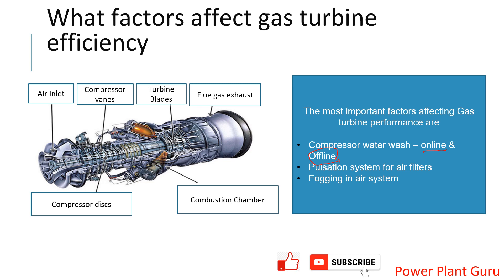Next is the pulsation system for the air filter. The inlet air filter system is very important for efficiency and heat rate. There is an online mechanism in each gas turbine where high-pressure compressor air is blown from inside out through the air filters. This cycle is repeated for a few filter elements at a time, dislodging dust deposited on the outside of the filters and keeping them clean. If the pulsation system in your plant is not working, you should check and do the required maintenance to restore it.